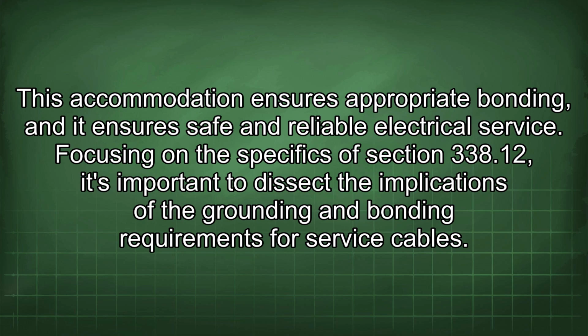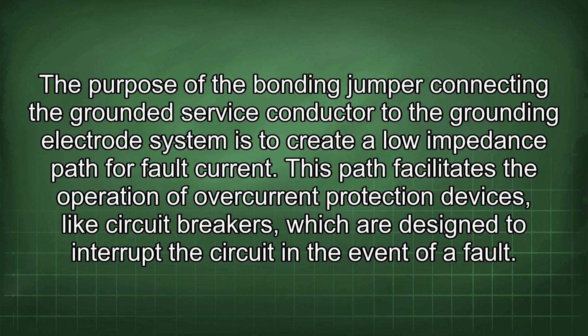Focusing on the specifics of Section 338.12, it's important to dissect the implications of the grounding and bonding requirements for service cables. The purpose of the bonding jumper connecting the grounded service conductor to the grounding electrode system is to create a low impedance path for fault current. This path facilitates the operation of overcurrent protection devices, like circuit breakers, which are designed to interrupt the circuit in the event of a fault.